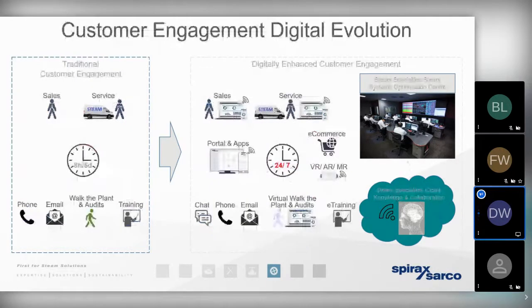So there are a number of key benefits here. For one, it means that if our client were to have an issue or a problem or any inefficiency with a process or a steam trap, there isn't going to be any lengthy delay between them identifying the issue, calling an engineer on site to diagnose the problem, and sending away for a service engineer to come back to site, sometimes on multiple occasions, to rectify a problem, all of which is going to have an ongoing impact with regards to energy efficiency, maybe even process and quality or health and safety implications. And if we've got multiple trips to and from site to rectify a problem, then of course there's a green and sustainability issue there.